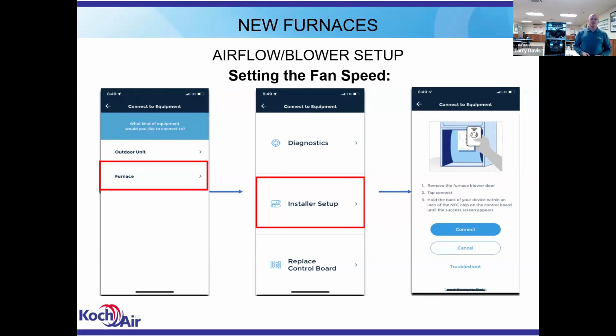Now you're going to use the near field communication. Once you select installer menu, it's going to tell you to remove the furnace blower door and then tap connect on your phone. When you're connecting to these furnace boards using the near field, the NFC connection, the board has to be off, no power. It's just like the card that you use to check into a hotel. It's the same technology. That door handle has a battery pack in it that powers up a board, and that little pass card that they give you has the information but doesn't have any energy in it. You just tap that to the door and it transmits that information. Or if you use tap to pay or a tap to pay app, it's the same concept. No power on the board when you're connecting to the NFC.